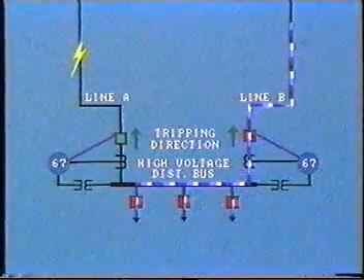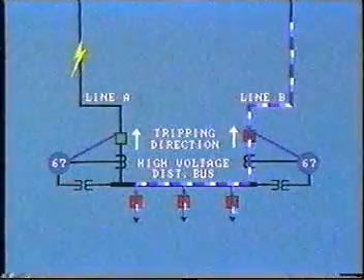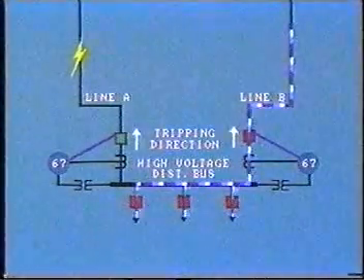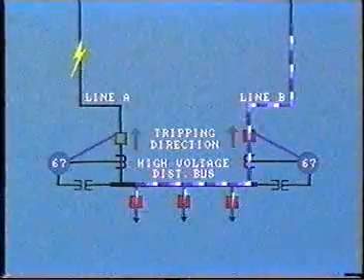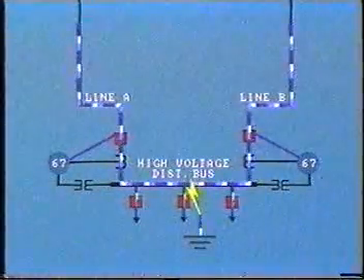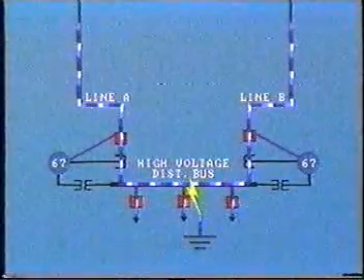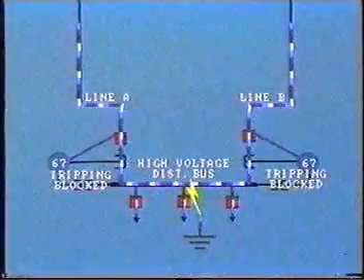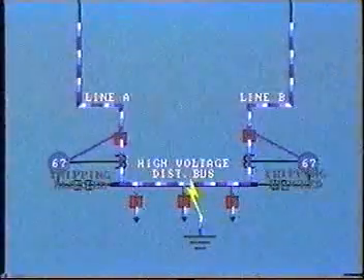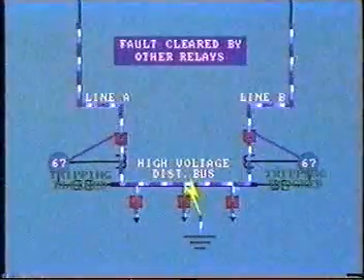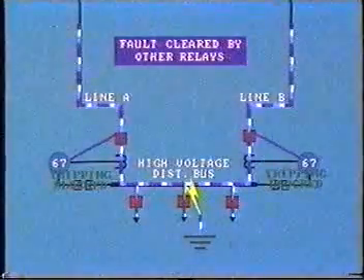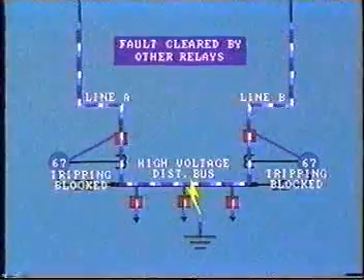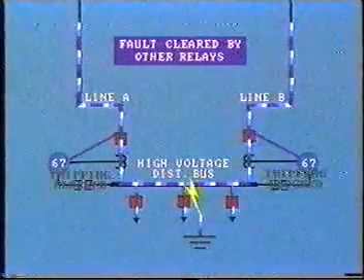For both of these lines, the correct tripping direction is when current flow is out of the bus into the line. In the case of a bus fault, current will flow into the bus from both feeders. Then both overcurrent relays will be blocked from operation by their respective directional relays. The fault would be cleared by other protection relays tripping out the same breakers — a clear case of zone overlap.